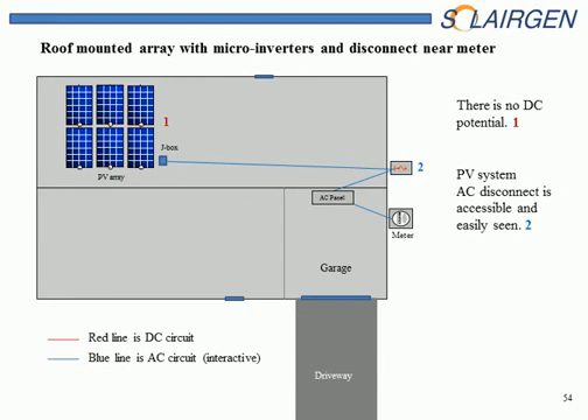Now in this drawing we see what is more typical these days, which is microinverters. With a microinverter you have no DC disconnect. Location number 1 is the DC. There are no load rated disconnects in this system. There are just microinverters up there, and at number 2 you have the AC disconnect. So this system is safe whether you pull the meter or throw the disconnect at number 2.